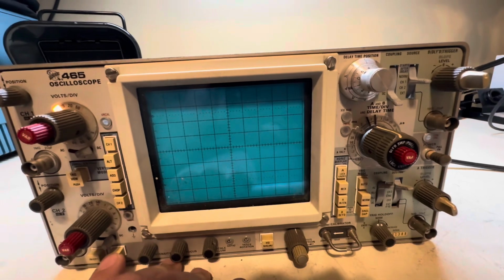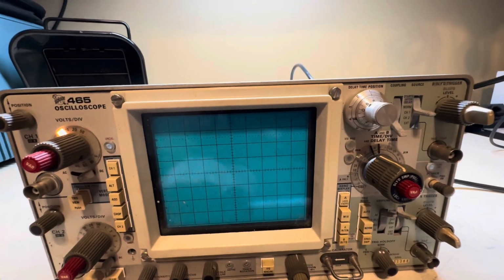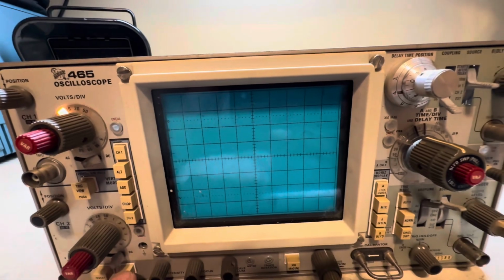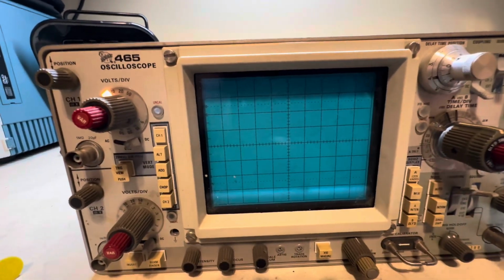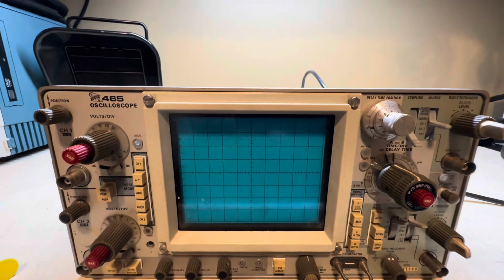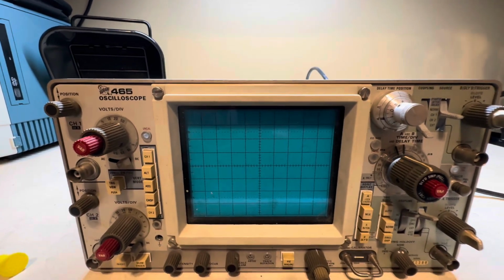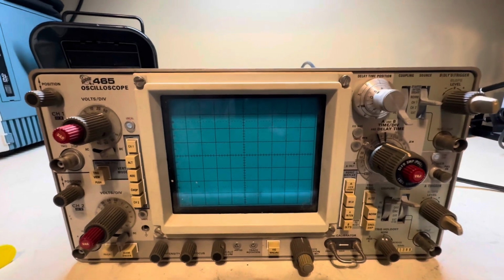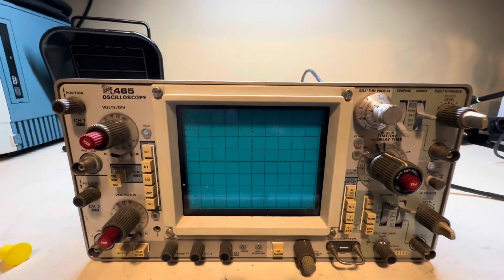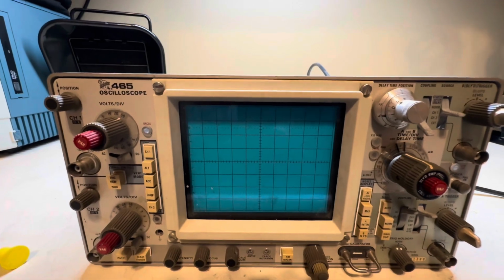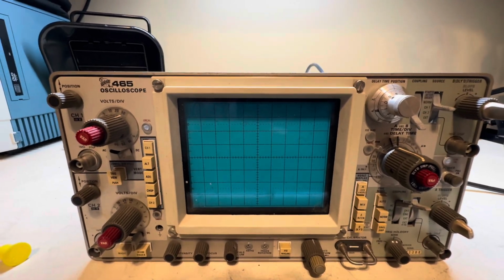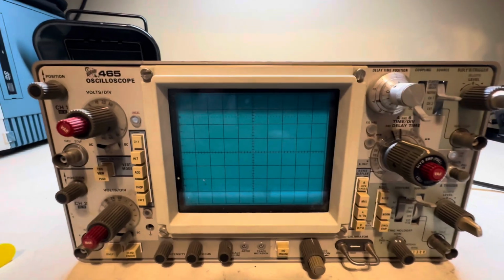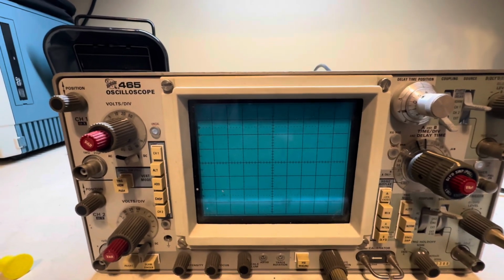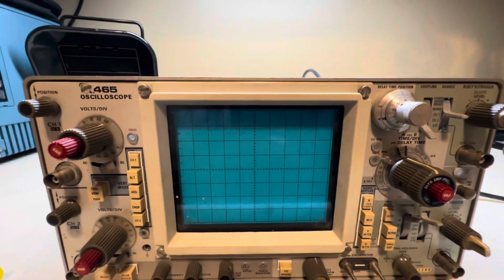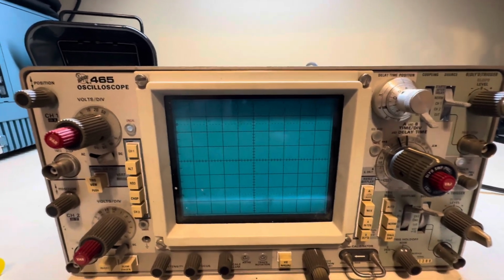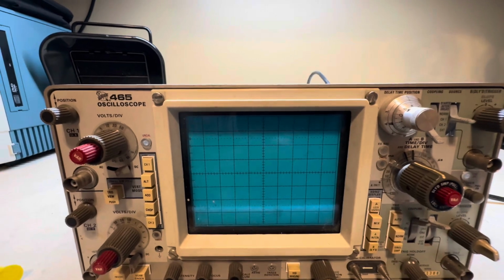And let's just see if we get a beam. And yep, nope, it's dead. Make sure the position's there. Try again, and nothing. So turn it off because I believe one of the voltage rails on the low voltage supply is shorted. That's normally what causes it. And I suspect it's probably gonna be the 15 volt rail, which is probably the first thing I'm going to look at. But I do want to get the full service manual printed, and that's going to be a lot of paper pretty much. But I like to do that because I like to have the schematic in front of me versus looking at a screen. It's much easier if I have to circle things, areas of interest and stuff.